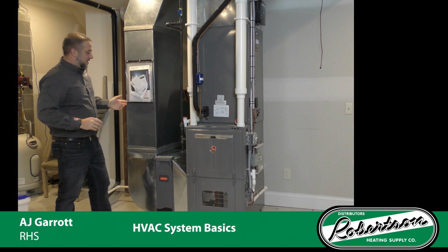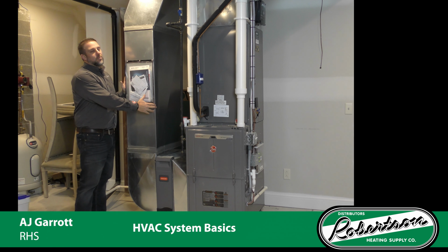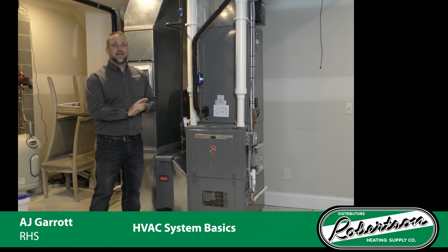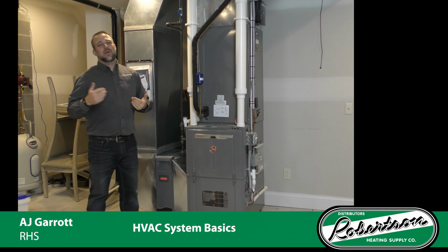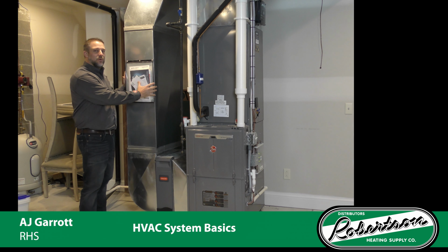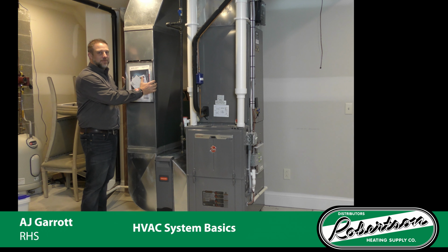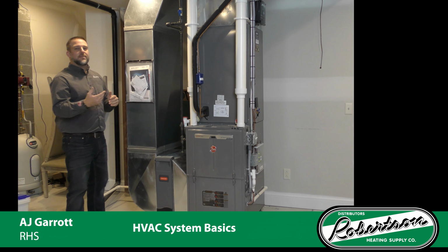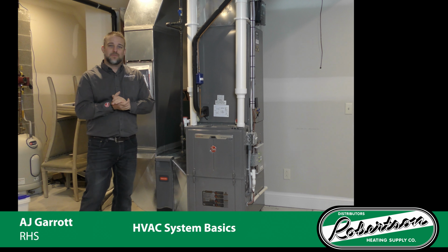Okay? The return duct is super important to make sure it's sized right. If we size it too small, we starve the furnace for air, and then we can run into any kind of error codes or furnaces malfunctioning and really shorten the life of a gas furnace or any kind of appliance like this. So it's super important we properly size this return air ductwork with that filter to make sure we have adequate enough air coming back to the furnace.